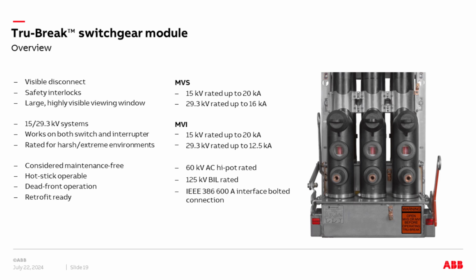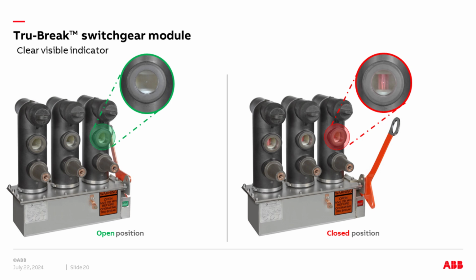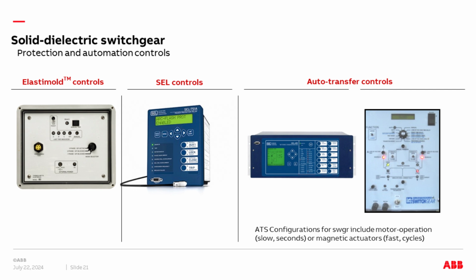I'm showing what's called the Tru-Break module. This is a mechanism that is attached to the front of the switch, and then it has interlocks with the switch, so you can physically open and see through the center window that the contacts are open. So this gives you a visual disconnect. So I should say many utilities require visual indication that the contacts are open before their crews are allowed to physically disconnect anything, pull cables, work on the equipment. So visible break can be achieved through this kind of a modular solution also. There's a little close-up of the window.